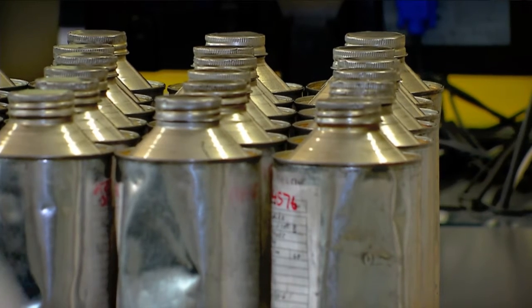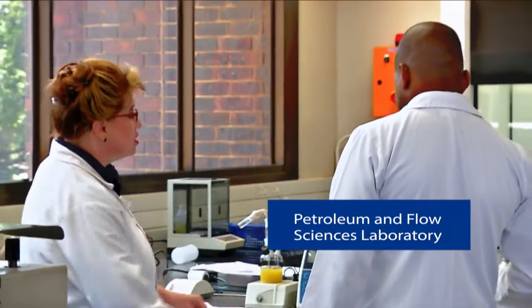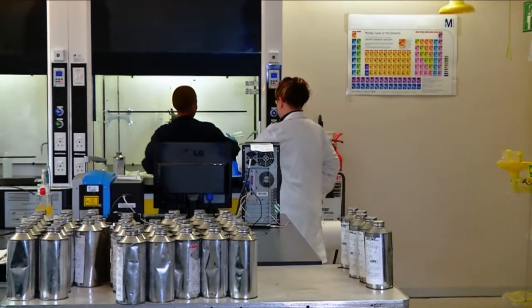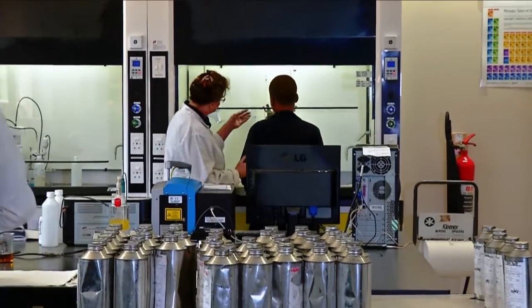This is the Petroleum and Flow Sciences Laboratory of Eskom, specifically the oil laboratory. When any transformer trips in the country, they're not allowed to put that transformer back into process unless they send a sample to us. We must do a test, and within 5 hours we must report the results. Because if they switch on that transformer and the reason it tripped is possibly due to a short, like arcing, gas is produced, and if you switch it back on, an explosion can happen.